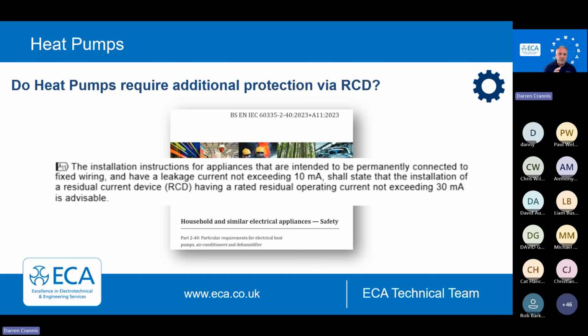So look out for what the instructions say. Often it's not required, and again, it's not all heat pump manufacturers. You might be second or third on site when it comes to this. The mechanical guys may be in first, and you may be in second. If you're not left with any instructions, you really need to ask the plumber and mechanical guys, can I have the instructions? Can I look through them? Because it may end up costing you a bit more, and you don't want to leave the client without a warranty, for example. Again, it's specific to each manufacturer. They have different requirements.